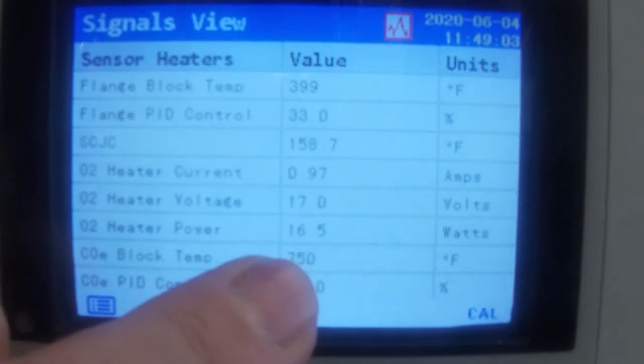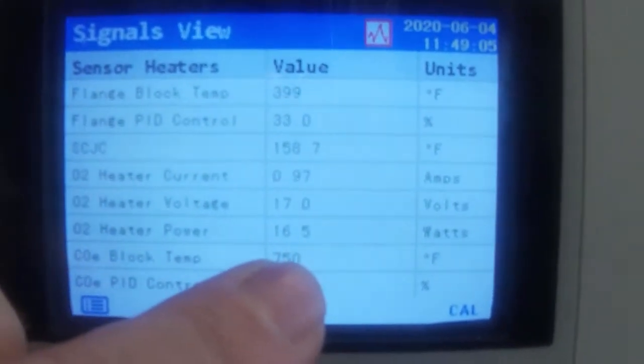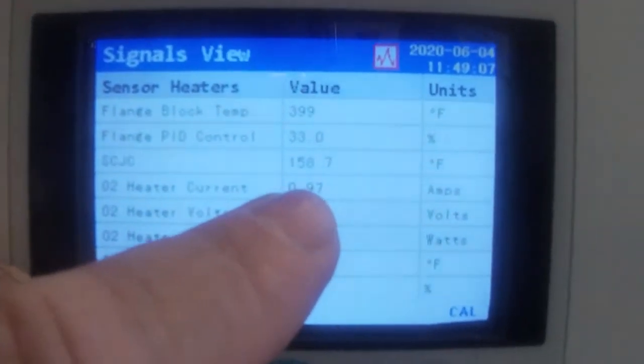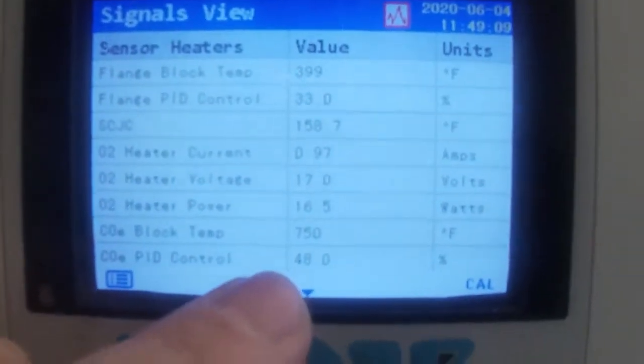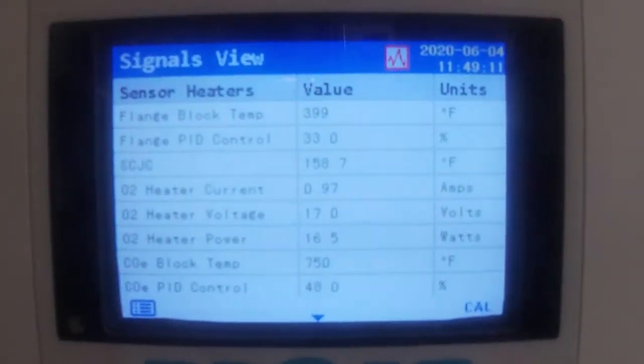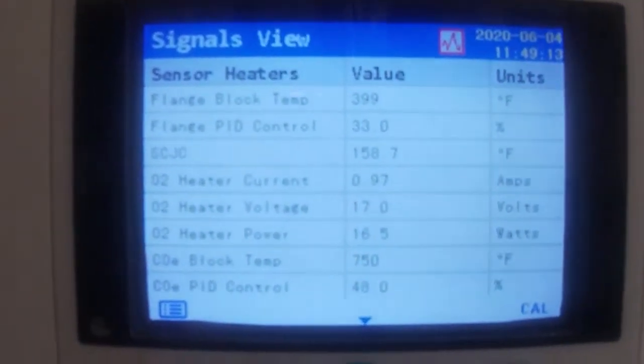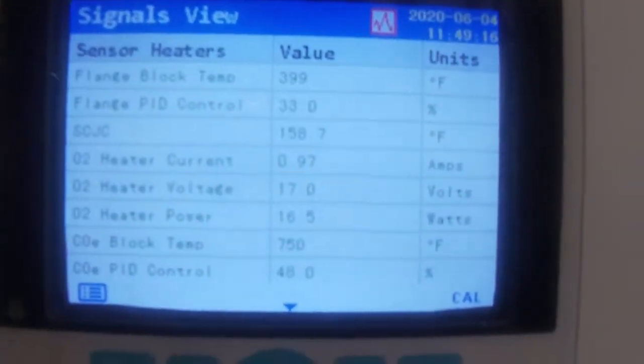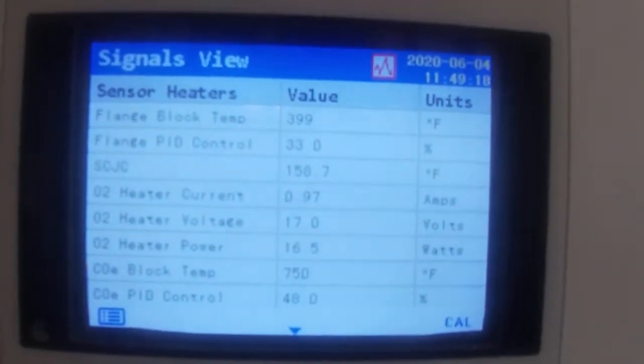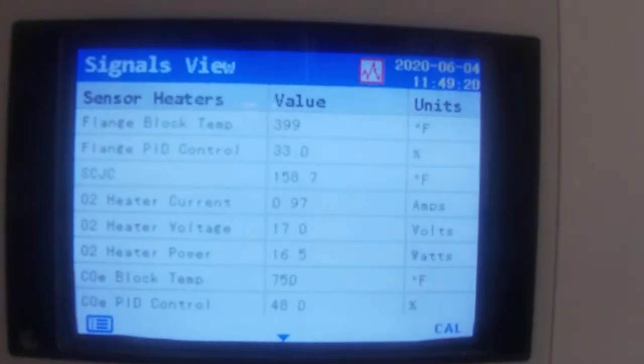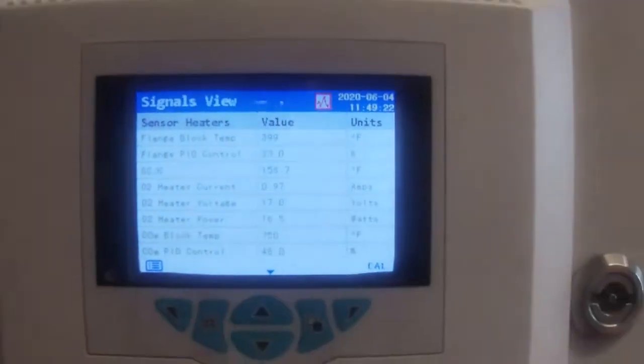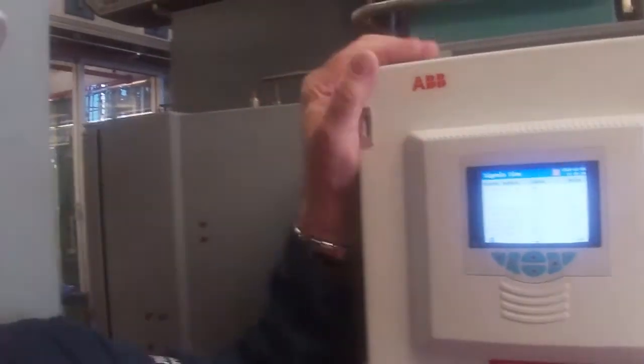The voltage on it is 17 volts. The power, okay, is sitting at 16.5 watts. That's nothing more than the current times the voltage. Then I said there was another block in there, a CO block. We actually take and elevate the temperature up again, this time to 750 degrees Fahrenheit.